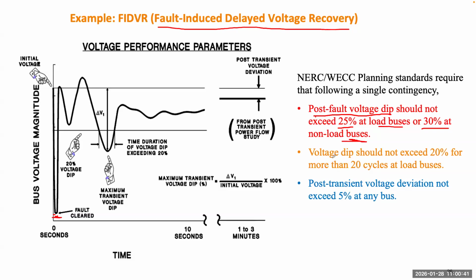The second sentence says the voltage dip should not exceed 20% for more than 20 cycles. So if the first one is satisfied, which means the voltage is higher than 0.75, and when it goes back there will be some oscillation. But you can see this waveform will temporarily go down. And if this line is 0.8, this is the duration for the voltage temporarily becoming lower than 0.8. That duration should be less than 20 cycles. 20 cycles is 0.33 second. If it's shorter than this, that is safe. That's okay. All right, so that's not finished yet.